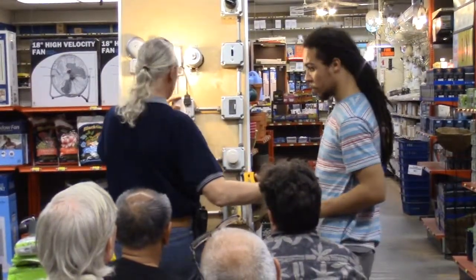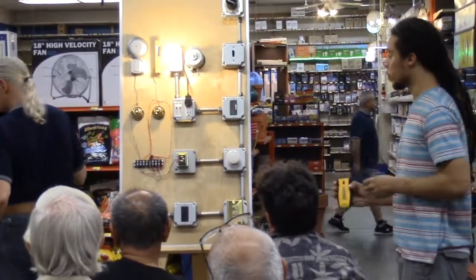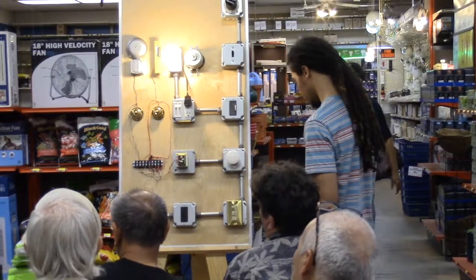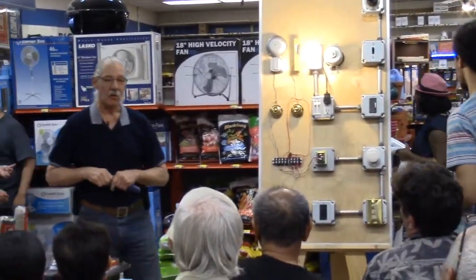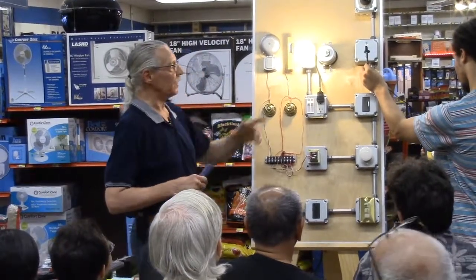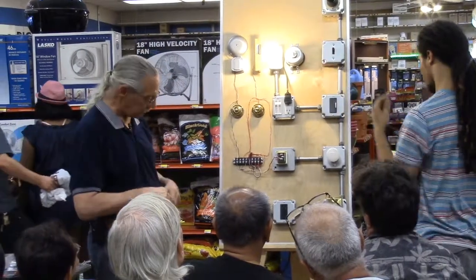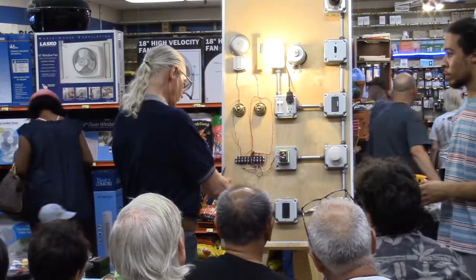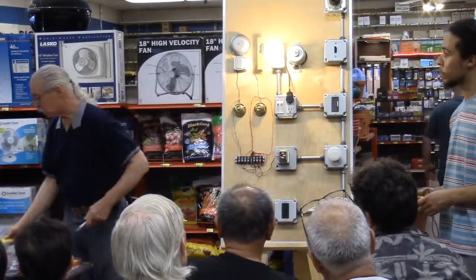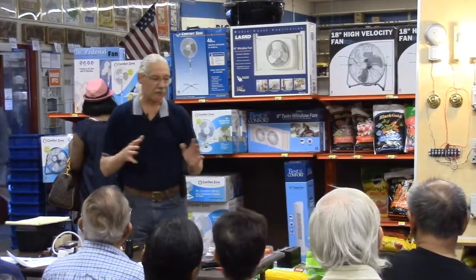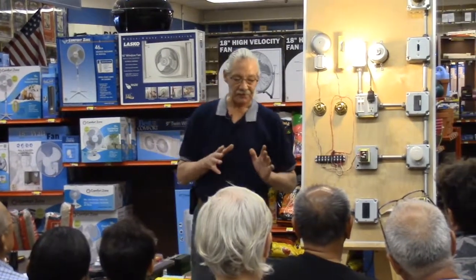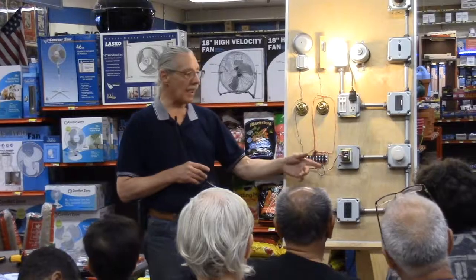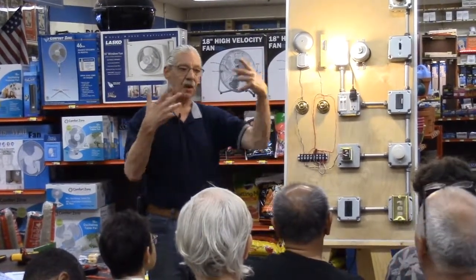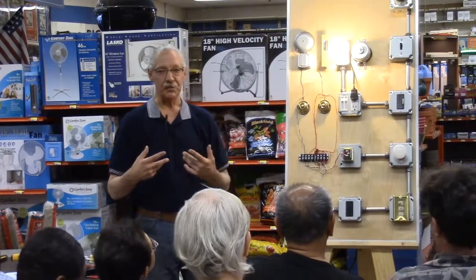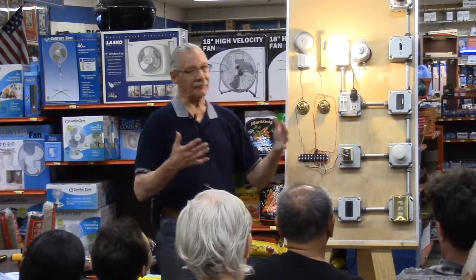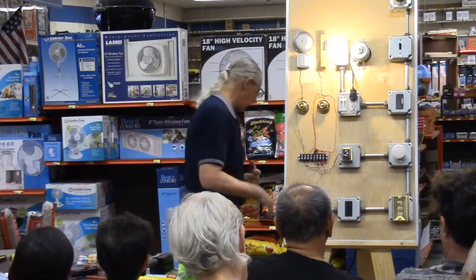So what in effect you're seeing here is that some of these things tend to, for want of a better word, be a work of art. As you can see, in this case, it's not lighting up when it should be. And the metal on most of your breaker boxes is a lot thinner than this, okay? But I've seen cases where it won't pick up the breakers until the cover had come off. So be aware that sometimes you have to take the cover off the breaker box in order to make it work.